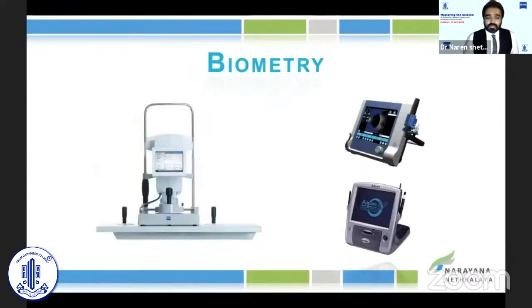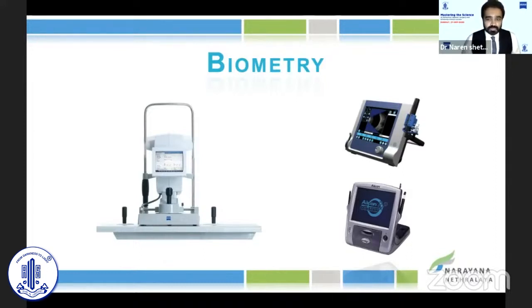For biometry, optical is the gold standard. Please try to stick to it because the results are extremely accurate. But if you don't have it, immersion is still okay. Do not try a contact method.